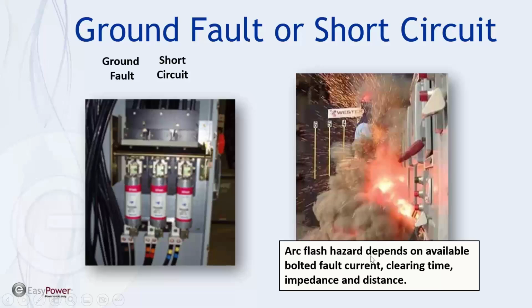And then there are other issues related to impedance and distance that will be a factor in what the arc flash level is as well. From a ground fault and short circuit standpoint, a ground fault is from a grounded point, so this is part of the box that's grounded. And then this one is short circuit, so if you have something between these two differences in potential, and when I say difference in potential, I'm talking about a voltage difference, then we've got a flash that could occur.